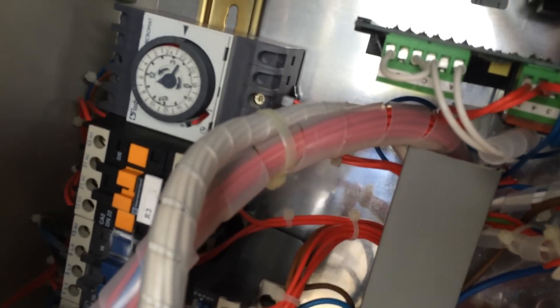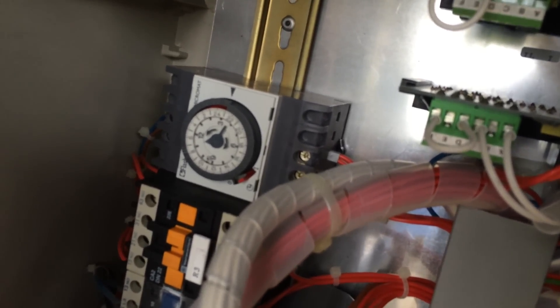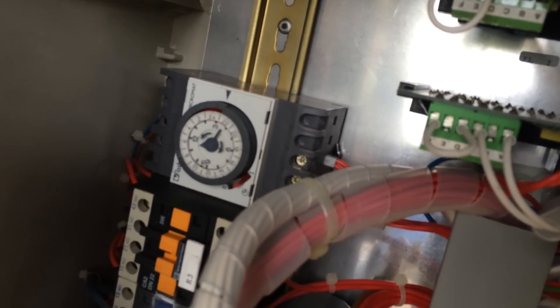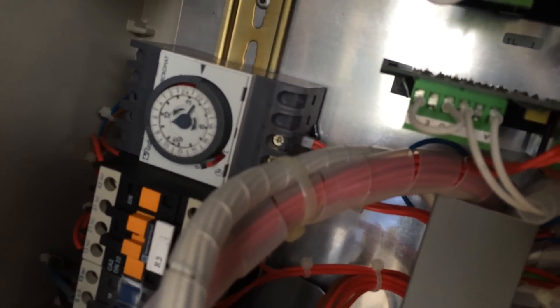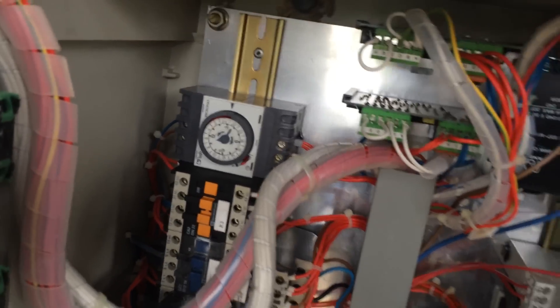Basically it will use the ice quicker than it makes it, so the quickest way it will cool is with a big ice bank. So yeah, that's not moved at all. So we'll check we've got power to it, but I'm pretty sure we have because it's just fed off a permanent live. So that's the problem I think here.